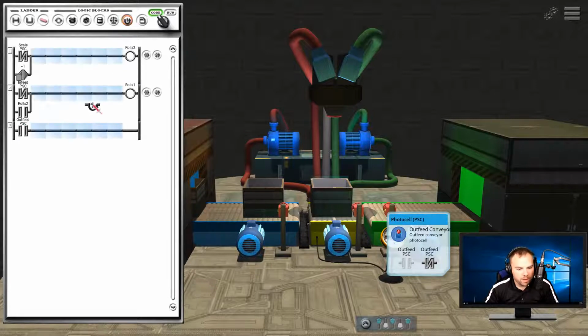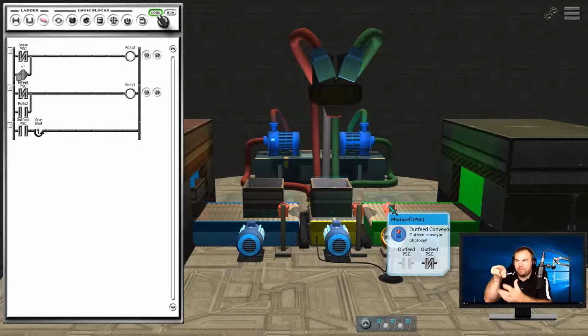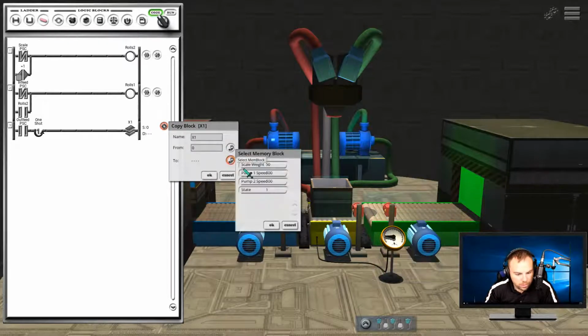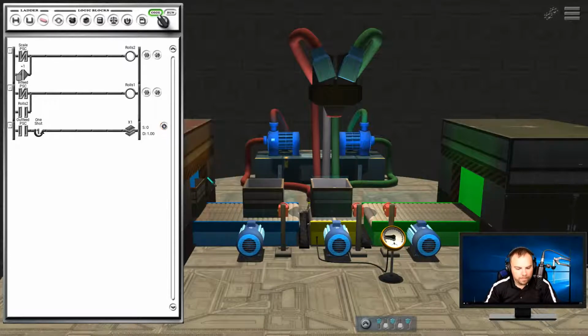We're going to do what's called a one-shot, meaning the code will only happen once, and then it's going to reset until it resets itself. Because as the scanner is scanning, if I had math in here, it'll just keep counting while it's high. The one-shot makes it so once it's triggered and set to high, it'll only run this line once until this trigger gets shut back off, and then it'll reset itself and do it again. So if it's high, we're going to do a copy. And we're going to copy the value of 0 to the value of state. Okay? So state will be a value of 0 again, and we can roll our motor. So state's 2, we can roll our motor.